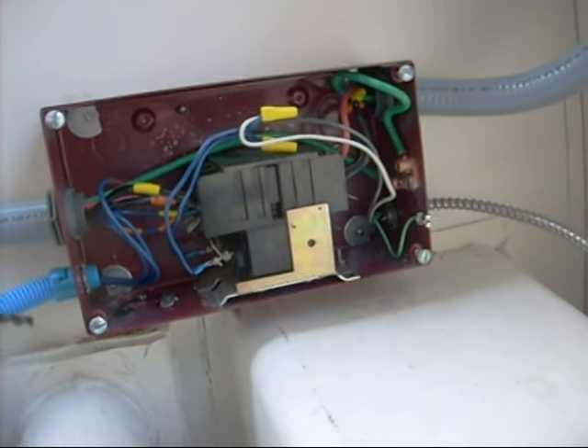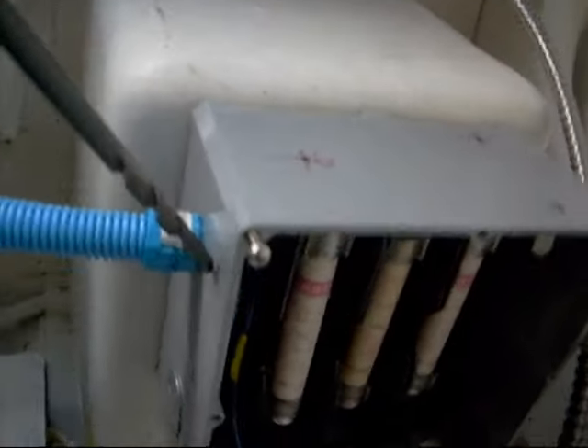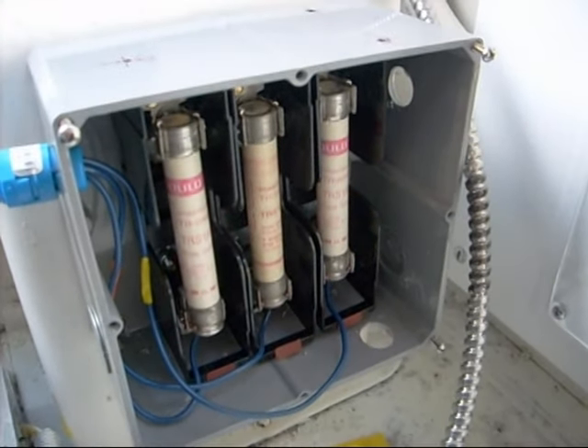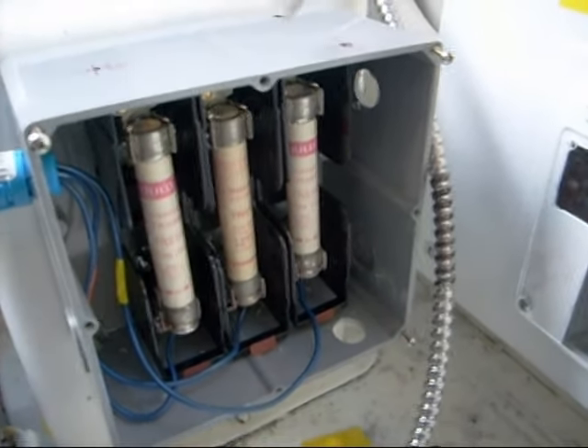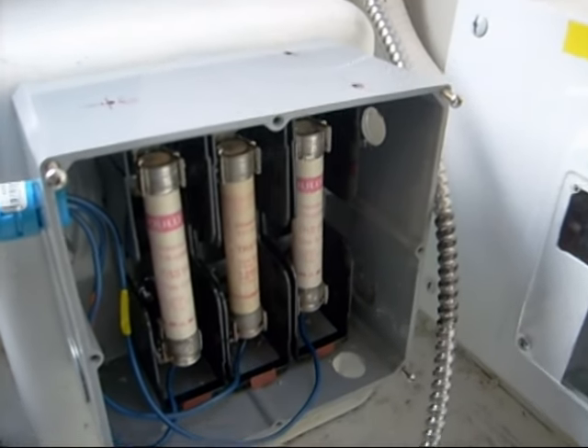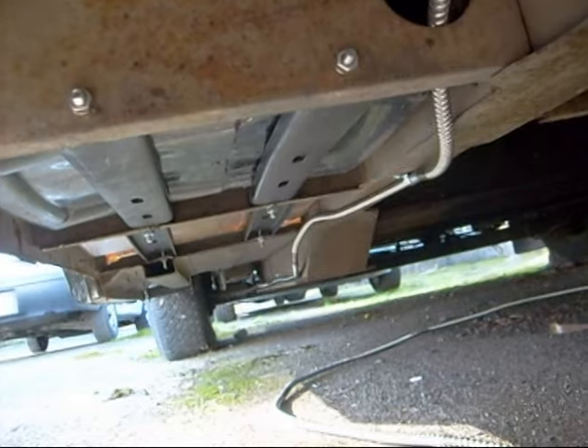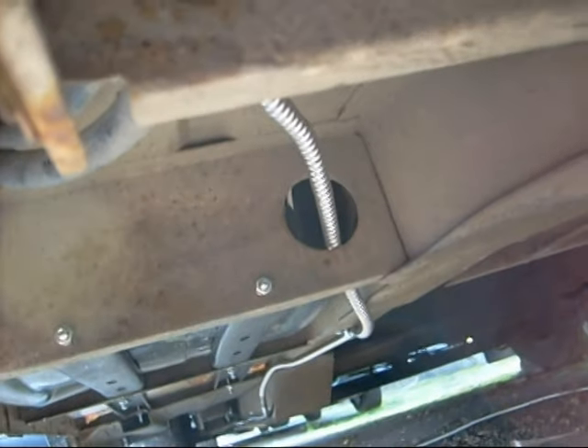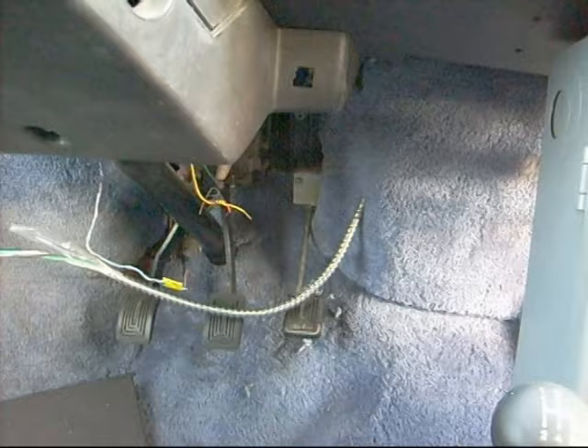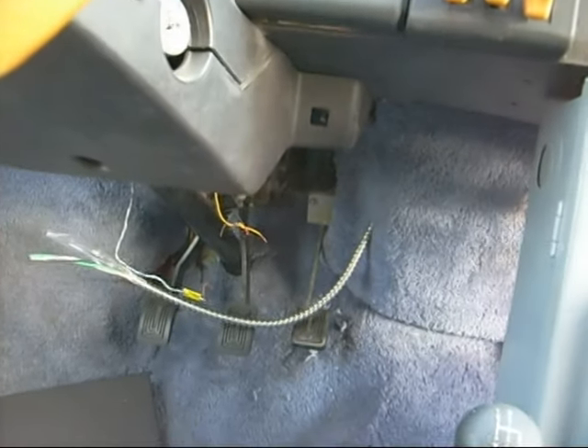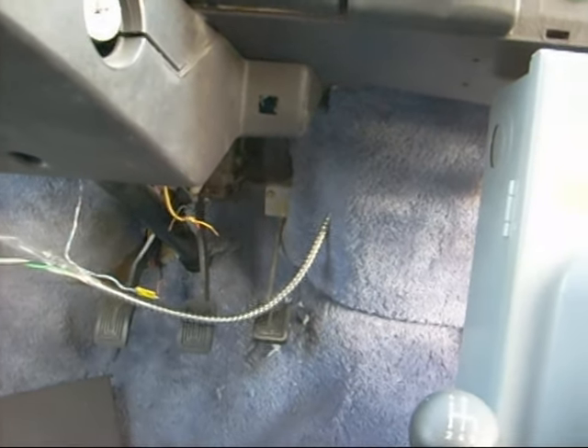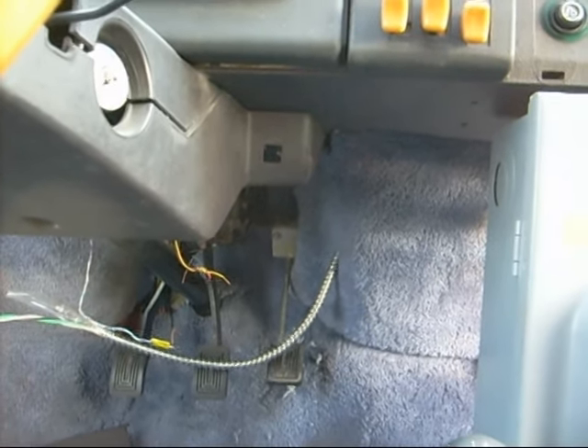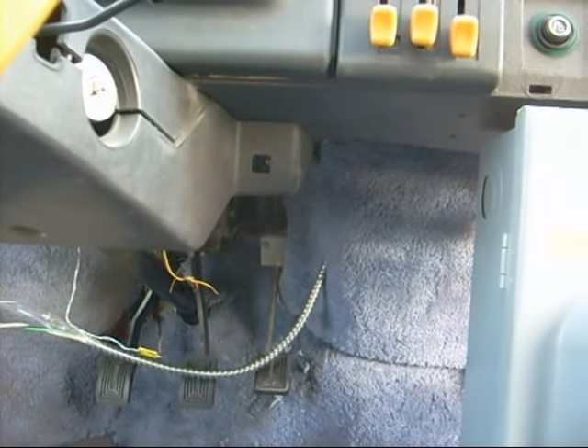In the contactor I've got three phases coming down this blue conduit into a fuse box. There are three one-amp fuses rated at 600 volts, and these fuses are in line to the ground fault detector. The MC cable is snaking through the chassis, supported by MC straps, and ends up just in front of the driver's seat through the firewall. It's going to go to a switch, then to an inverter which will give us 120 volts to turn the contactor on and off.